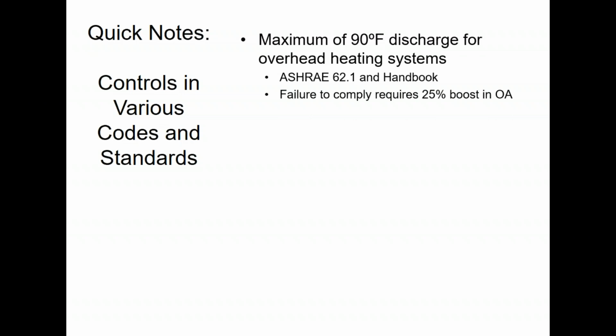Your space temperature is 72. Your maximum supply temperature is 87. If you don't do that, ASHRAE 62.1 will kick in extra rules for your ventilation effectiveness, which will actually end up requiring you 25% more outside air CFM than you otherwise would have had to do. All right. So keep that one in mind. That one's pretty easy to comply with.